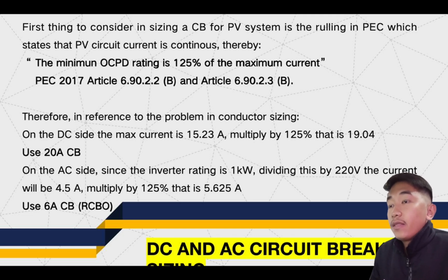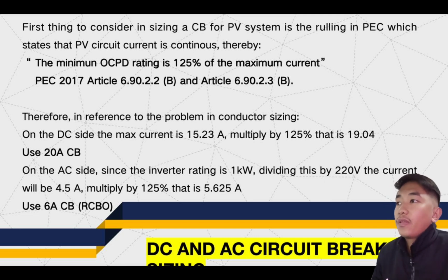Therefore, in reference to the problem in conductor sizing, on the DC side, the max current is 15.23 ampere. So we multiply by 125%, that is 19.04. So wala tayong mabibili na exact current na 19.04 ampere. So titingnan natin sa table, ang pinakamalapit na pwede natin gamitin ay 20 ampere circuit breaker on our DC side.